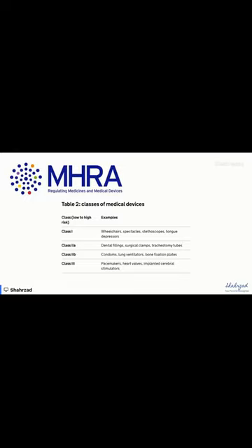Now, I just wanted to highlight one thing here. Pacemakers. Active implantable medical devices, which are pacemakers and the likes of that, are called AIMDs. They require an external power source or rely on an internal power source and remain implantable. All AIMDs are covered under a separate directive in the EU regulatory system.